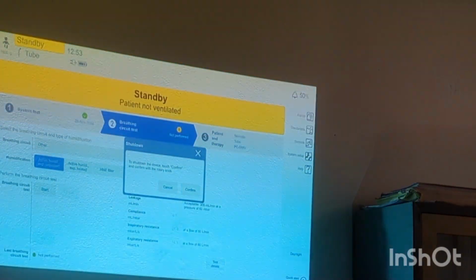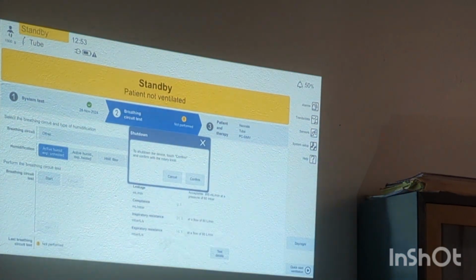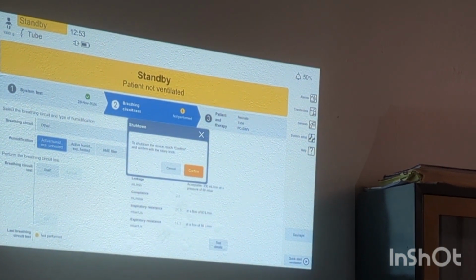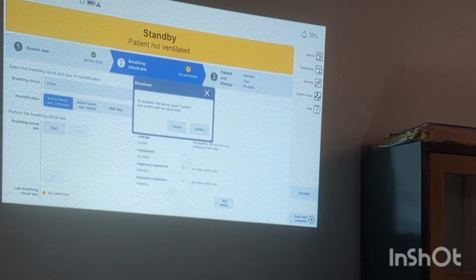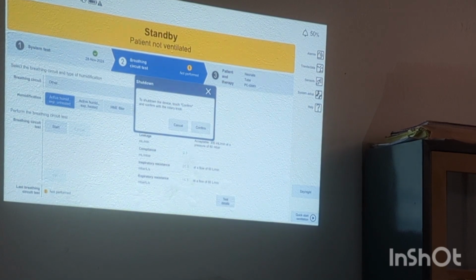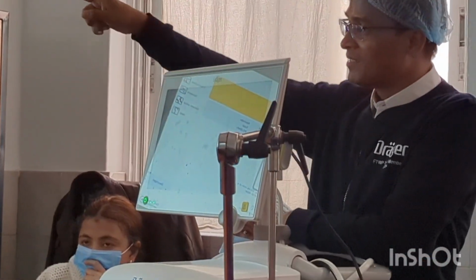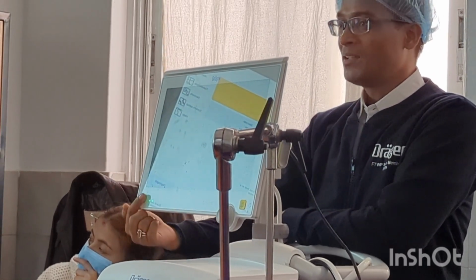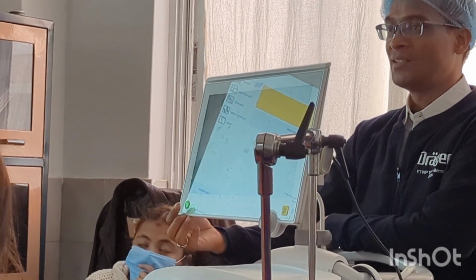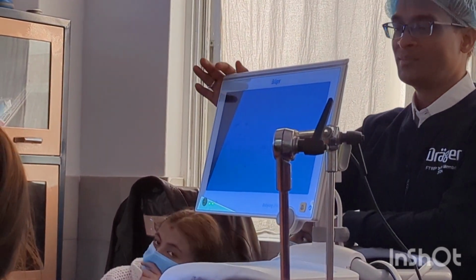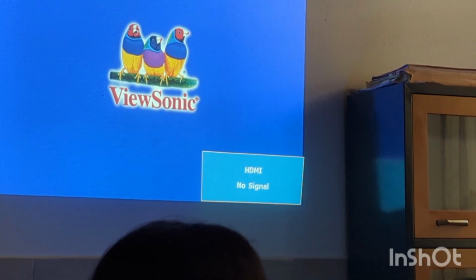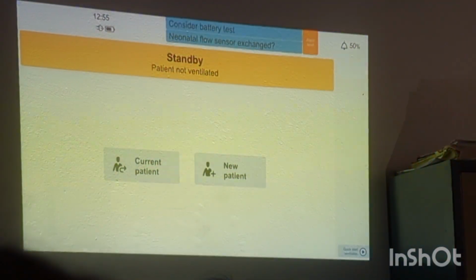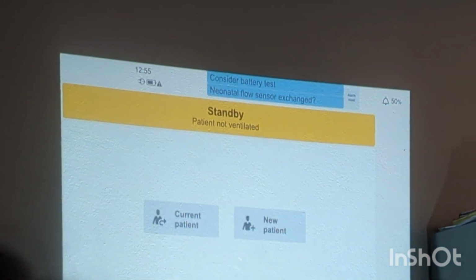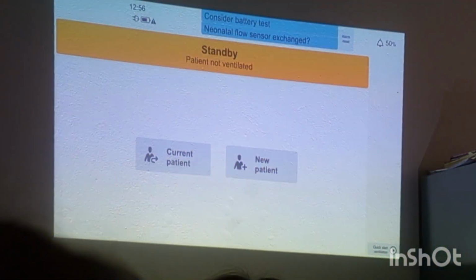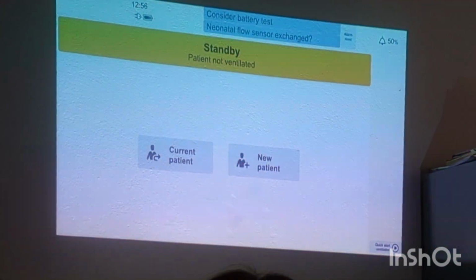Suppose this feature is not there. If I press it here during ventilation, unfortunately, if it is connected to the patient, it will get shut down. So that is one safety feature, so we want to confirm. Then again this is one more step of safety feature. You can see the device is blank, but the device is not yet turned off. You should wait till this power LED is gone. When this green indicator is completely off, now the device is dead. Just wait till this LED goes off. Consider the battery test. Here you can see near the battery symbol there is a warning symbol, continuously flashing. So this machine has one more feature, the battery test.